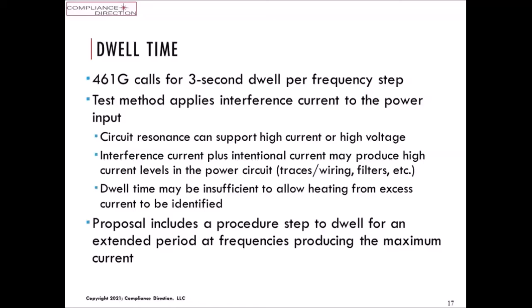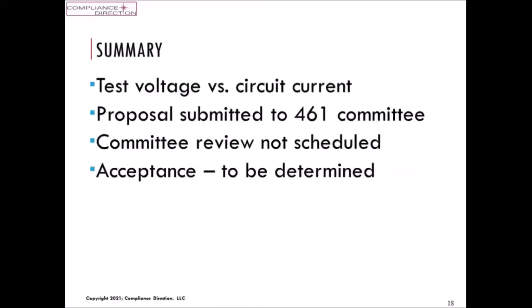The wire is starting to smoke, so if that frequency was present as a real interference, it could be there longer than 3 seconds. So I'm proposing a procedure step to dwell for an extended period at frequencies where the current's being elevated. That gives us a chance to evaluate that. I believe I put in at least 2-minute dwell time at resonant frequencies producing high current levels. So basically, we use the test voltage or circuit current. I'm proposing we use the current as a control measure. Apply the test voltage and use the current as a control measure.